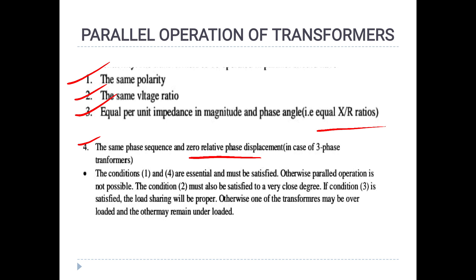The 4th condition is same phase sequence and zero relative phase displacement. The main condition for equal load sharing is the third point — equal per-unit impedance in magnitude and phase angle. Per-unit impedance and phase sequence must be the same, and we must have equal X/R ratio. This ensures equal load sharing between the parallel transformers.